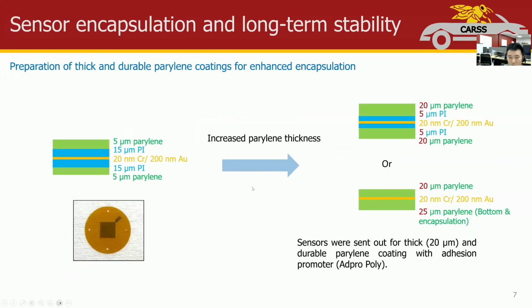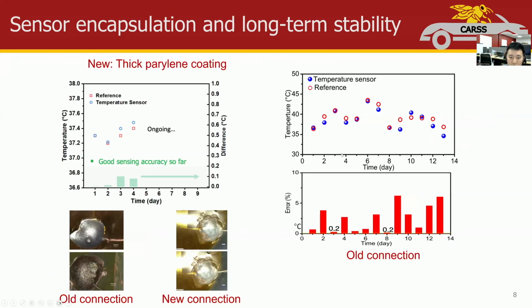Based on this, we then change our Parylene layer from 5 micron to 20 micron, as you can see on our right-hand side. Here we have 20 micron Parylene on both sides of our sensors. Subsequently, we re-evaluated the long-term stability of the sensor. The data indicates that using a thicker layer of Parylene significantly enhances performance. Clearly, our newly designed temperature sensor equipped with this thicker Parylene coating demonstrates improved longevity. Long-term testing is still ongoing, and we will provide a comprehensive summary upon its completion.